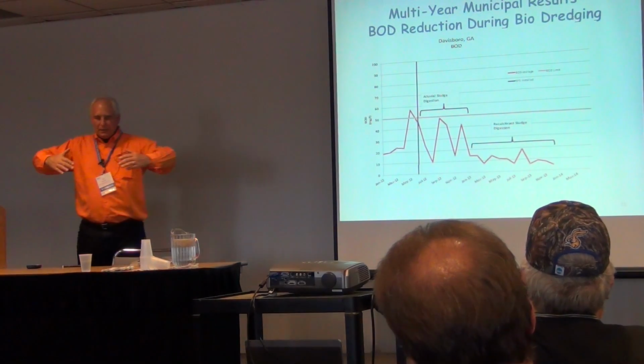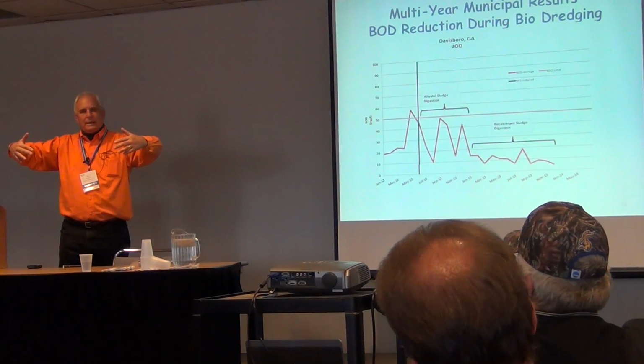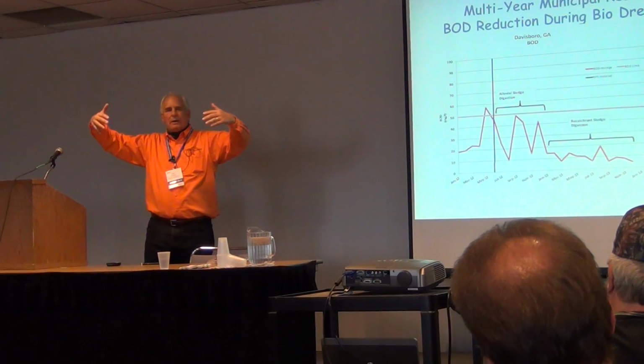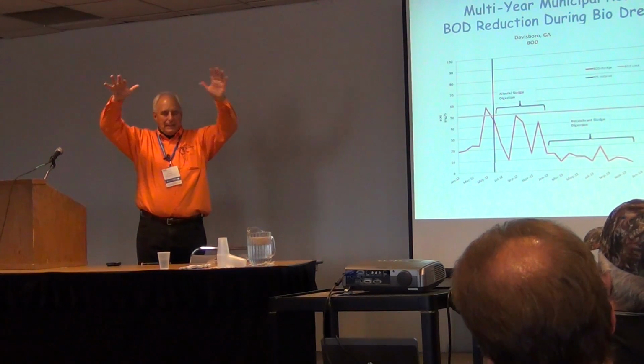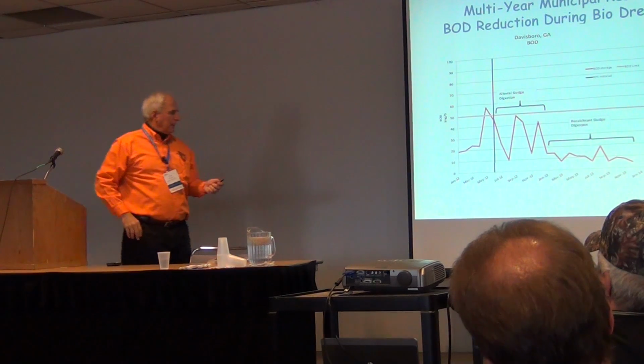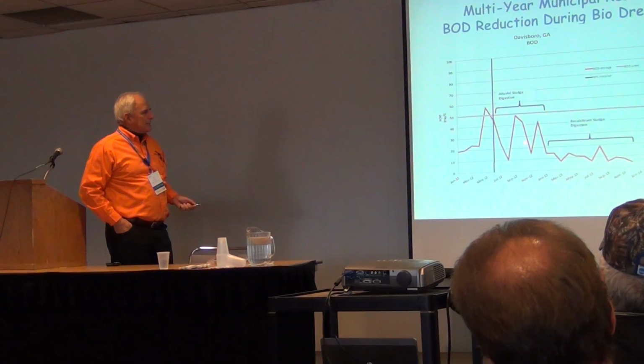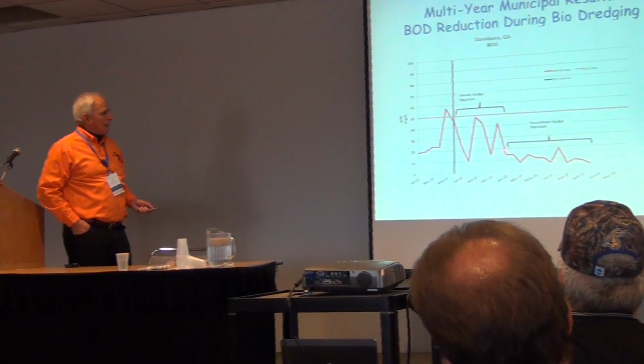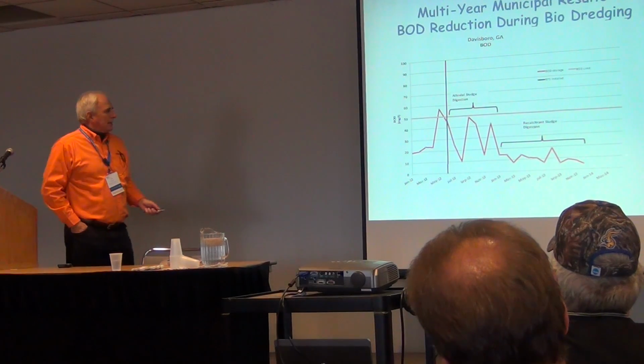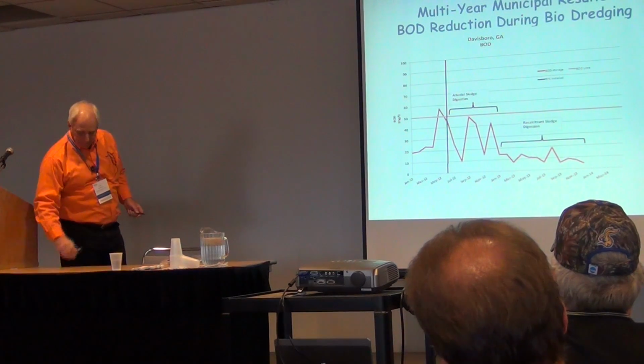What happens is you can get big desktop-sized pieces of sludge that the gas occludes to, and it raises it up. You've all seen eruptions in your ponds, okay? And then the gas is released, and it rains back down, but now it's broken up. And so when you get a big eruption, you get a BOD spike. And the system eats the BOD, and then another eruption comes up. But once the alluvial sludge is gone, and now you're just attacking the gel sludge, then that gel sludge is just taken off one bologna slice at a time.